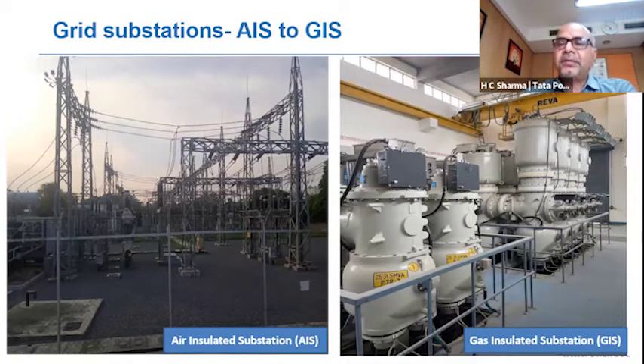Of course, it is low in maintenance, and environmental factors like storms are not there. It is a weather neutral type of substation. It doesn't get affected much by the weather conditions unless water enters into the substation and damages things. One challenge which remains with the GIS, which needs to be discussed, is that whenever a GIS substation goes down because of any maintenance issue, it cannot be repaired in a very short time as in an AIS substation. Suppose in an AIS substation anything happens, everything is visible and it can be corrected very fast. So it is low in maintenance but high in MTTR. The mean time to repair, or mean time to restore, is a little high because you have to open up the equipment, diagnose, get the equipment, and then the repair takes more time. So that is one of the challenges with GIS substations.